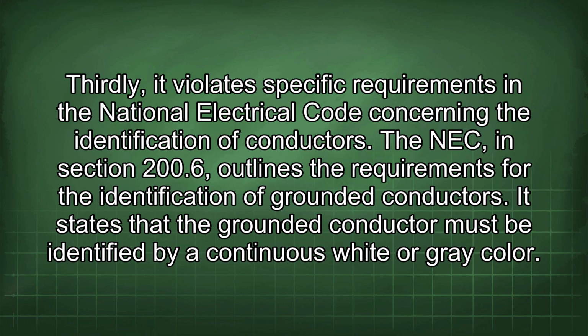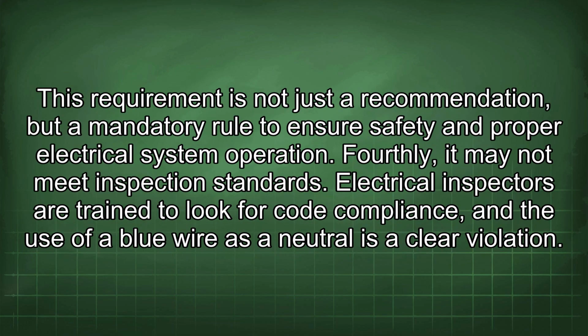Thirdly, it violates specific requirements in the National Electrical Code concerning the identification of conductors. The NEC, in Section 200.6, outlines the requirements for the identification of grounded conductors. It states that the grounded conductor must be identified by a continuous white or grey color. This requirement is not just a recommendation, but a mandatory rule to ensure safety and proper electrical system operation.